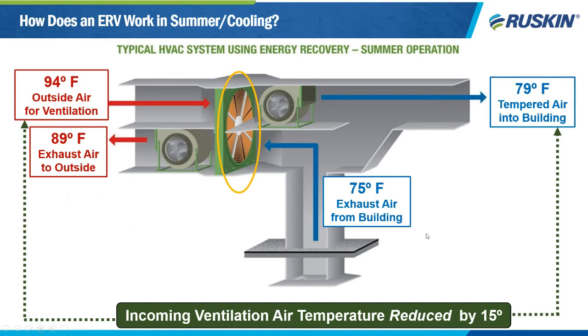So let's isolate the ERV and really get into how an ERV works. What you're looking at here is a typical summer day in Kansas City. Ruskin is based in Kansas City. This is real ASHRAE data that we're using here, typical summer day design conditions. What you see is 94 degree hot, humid air outside. You also see 75 degree air in your space, in your building, most likely like the air in the room that you are sitting in listening to this webinar.